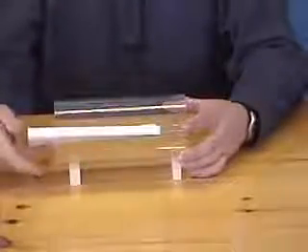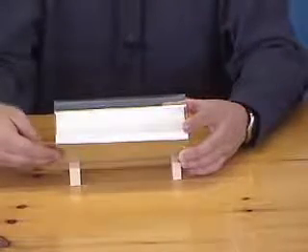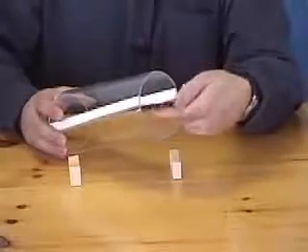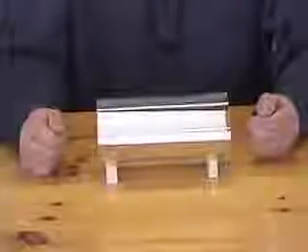That process will pull heat away from the plastic, which will in turn pull heat away from the adjacent airstream. When you come out the other end of this long imaginary tube, the air on the plastic side will be dry, and it will be close to the wet bulb temperature of the entering airstream. This is indirect evaporative cooling. It is both a heat and a mass exchange process.